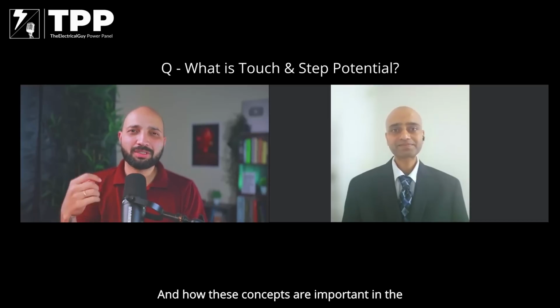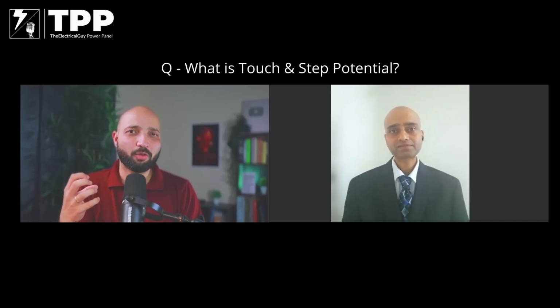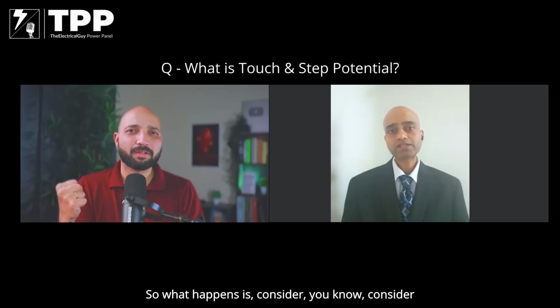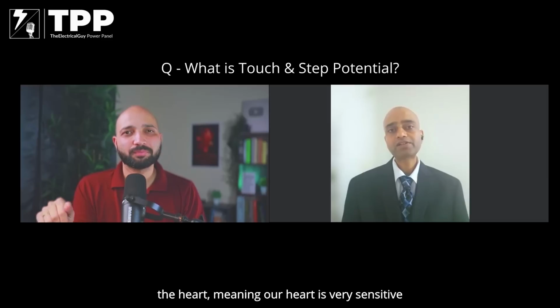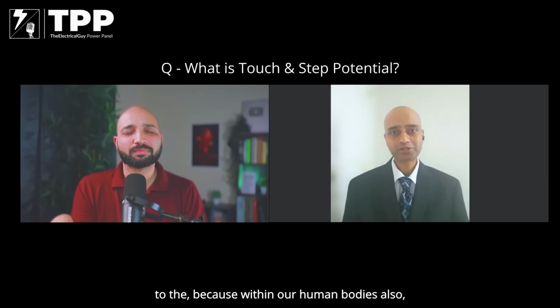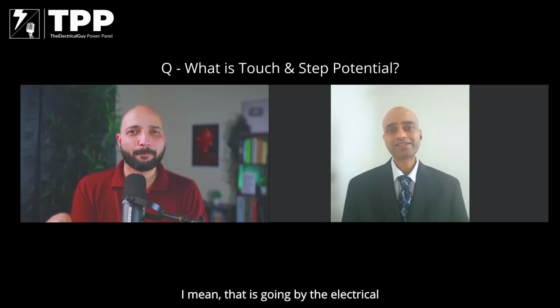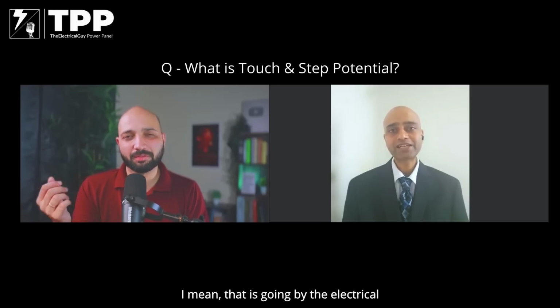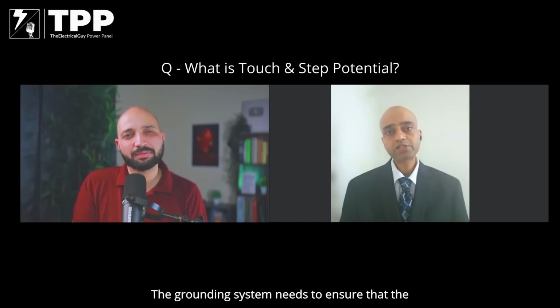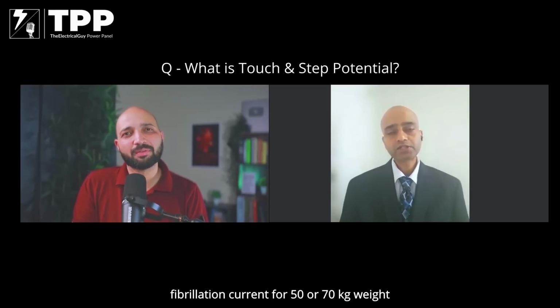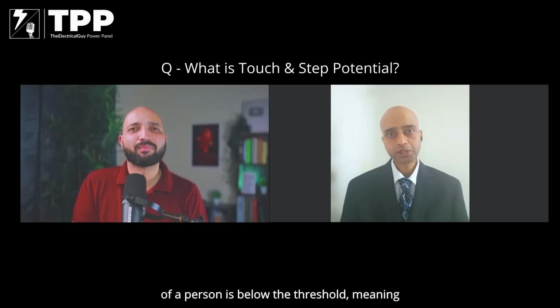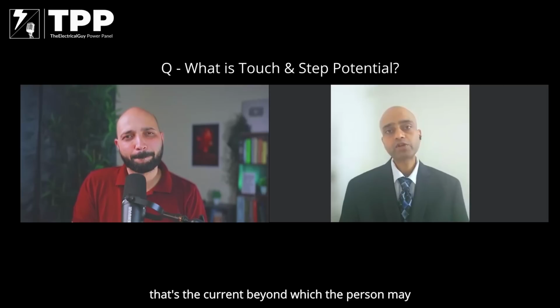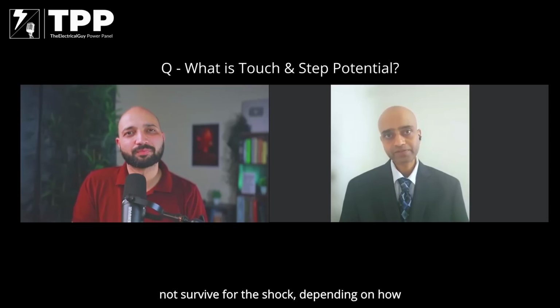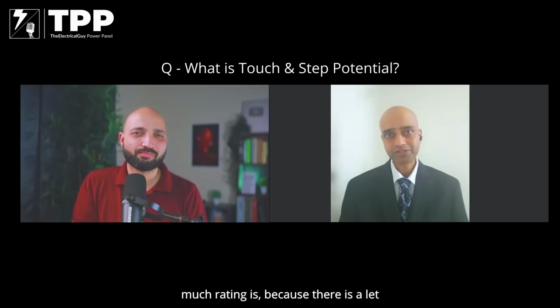How are these concepts important in grounding? Consider the heart—it's very sensitive because our human body is governed by an electrical system. The grounding system needs to ensure that the fibrillation current for a 50 or 70 kg person is below the threshold, meaning the current beyond which the person may not survive the shock, depending on the rating.